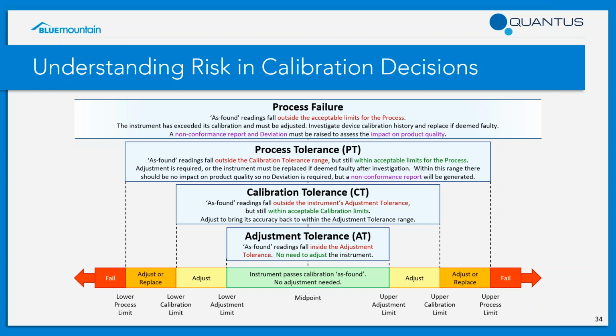The next one up defines the process tolerance. Here, the as found readings fall outside of the calibration tolerance range, but still within acceptable limits for the process. So adjustment is required, or the instrument must be replaced if it's deemed faulty after some sort of investigation. Within this range, there should be no impact on product quality, so typically no deviation would be required, but a non-conformance report would be generated. Again, I'm talking about the Blue Mountain software, which has that non-conformance functionality as a standard feature. In this case, the as found readings would fall into the gold colored areas to the left and right of the bar down the bottom.